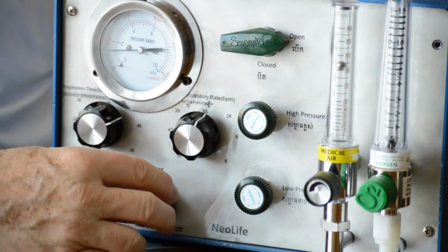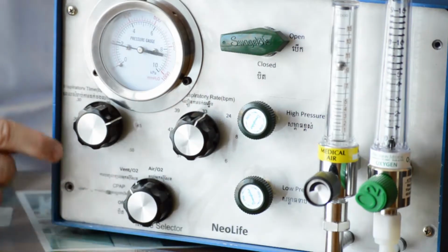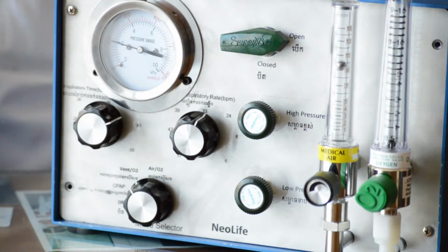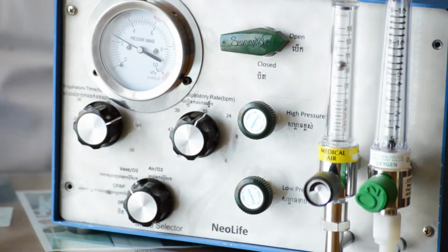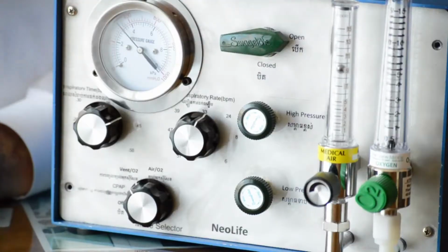Sometimes, though, they have apneic episodes where they're not breathing very well, not effective breathing anyway. And so you want to give a few breaths. And this machine has the ability then to just turn it on. And then, as you can see in the gauge, the baby is getting breaths on top. You can adjust that from a rate of 30, 35, 40, 45, 50, 60, whatever you need in there.